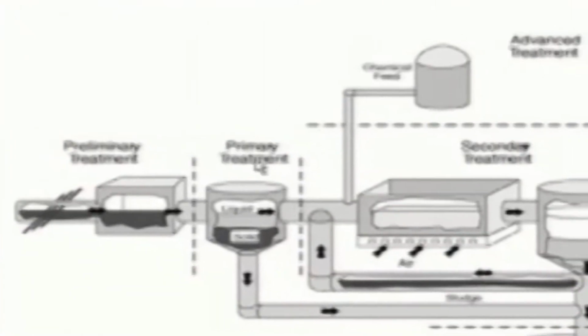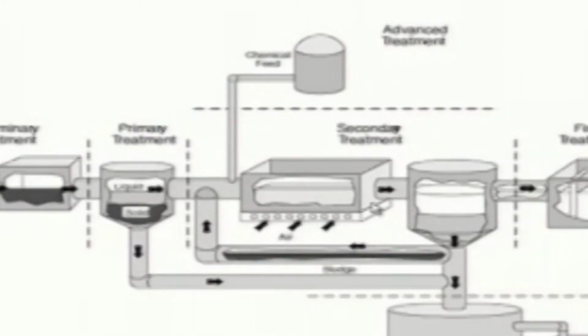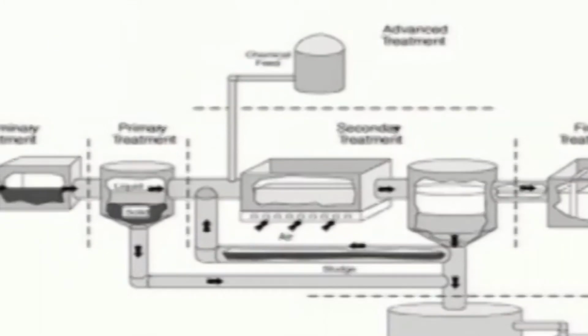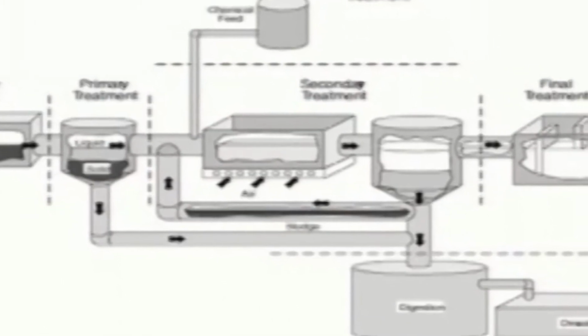The primary treated effluent is fed into the aerobic process. There we have an aeration facility followed by a secondary settler. In the aeration tank, air is forced into the reactor in order to keep aerobic organisms alive. Subsequently, the mixed liquor is collected in the secondary clarifier. Part of the active microbial population is sent back to the reactor to maintain the bacterial population at a constant rate.